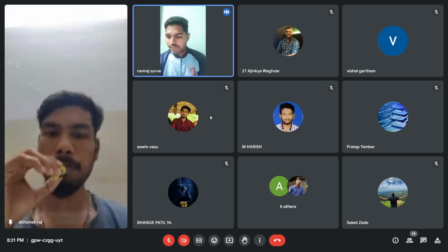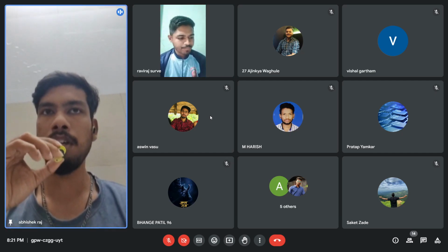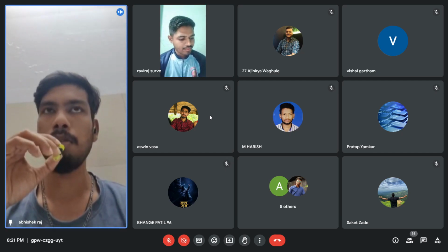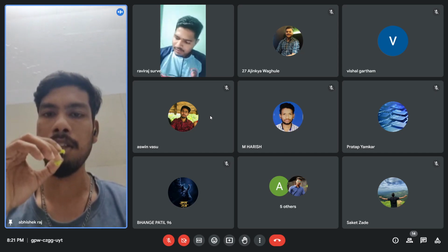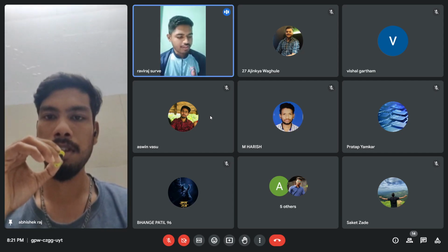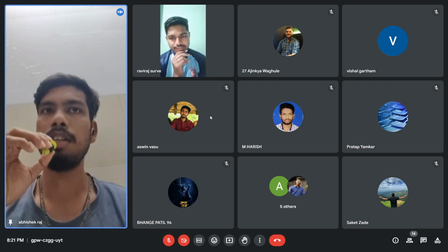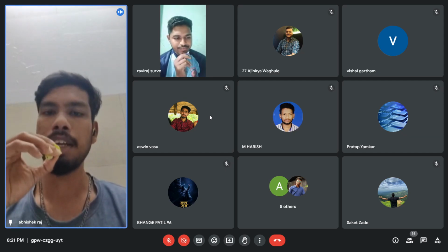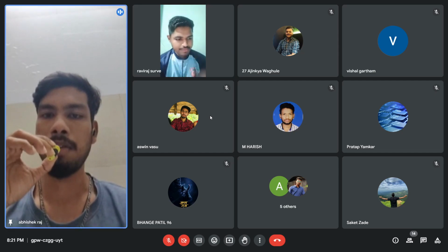Okay, Abhishek. Do you know which types of refrigerant we use nowadays? Nowadays we use HFCs. Most commonly we use R134A, which is tetrafluoroethane. Okay, if we use R134A refrigerant, what is the temperature and pressure in the condenser? In the condenser it will be 30 degrees Celsius, and pressure will be 10 bar if you use R134A.